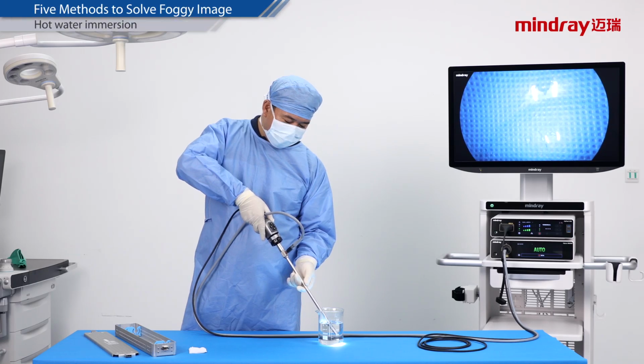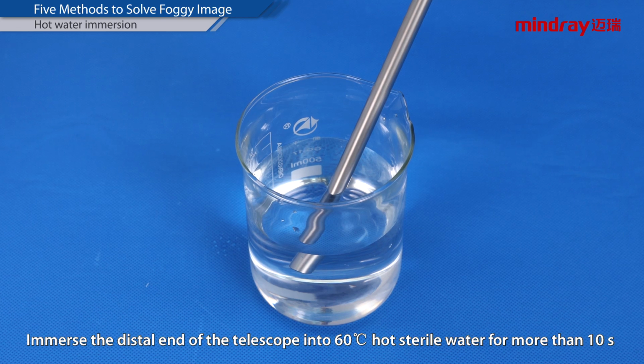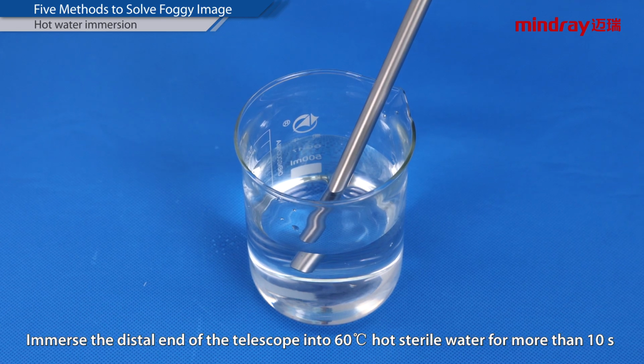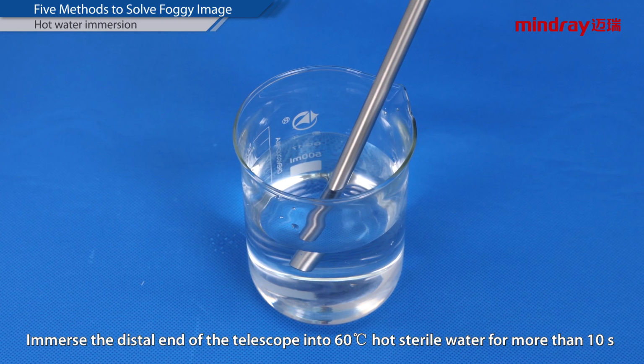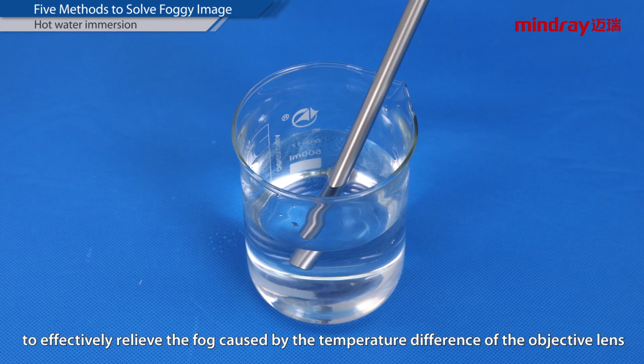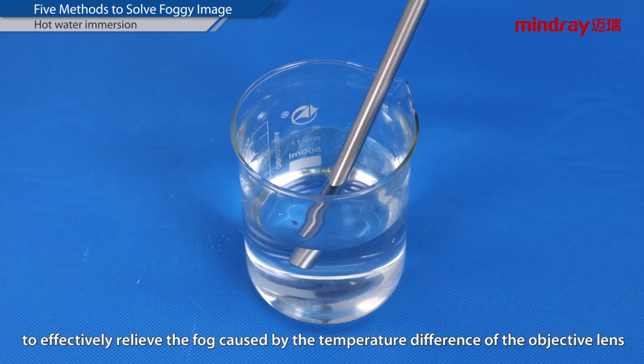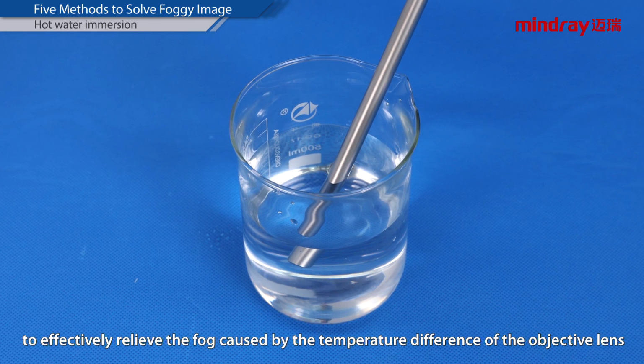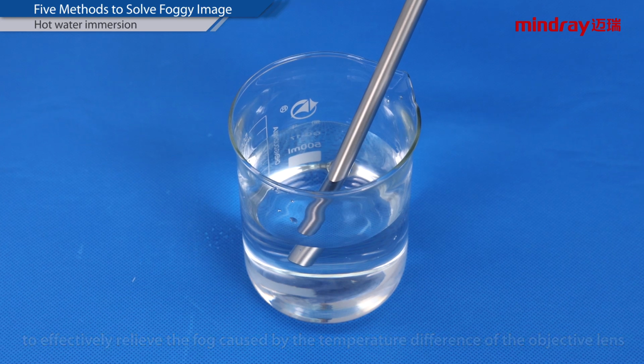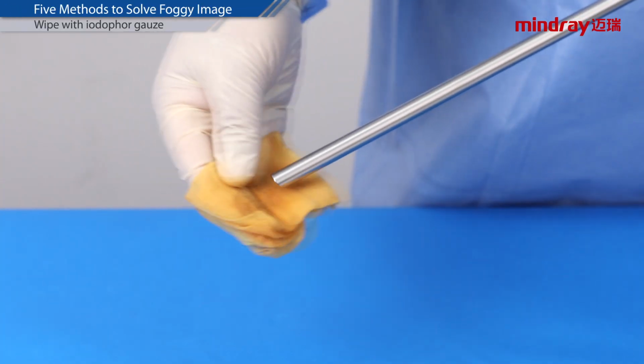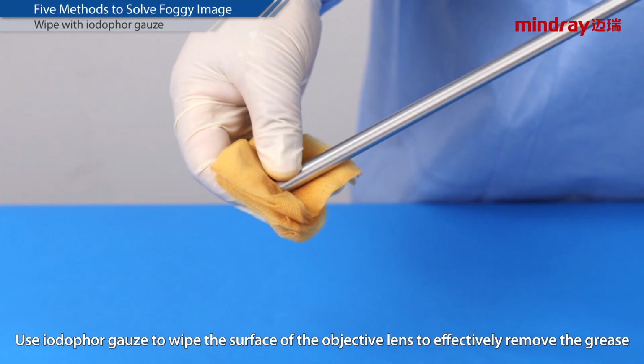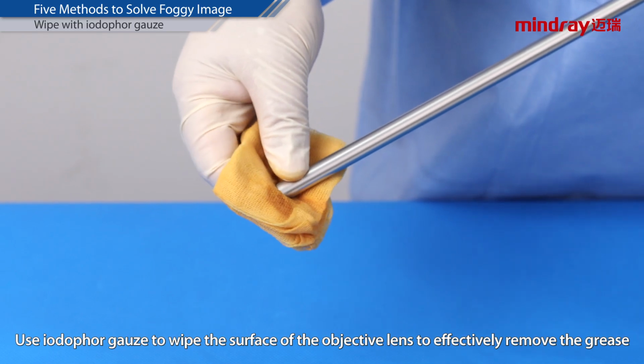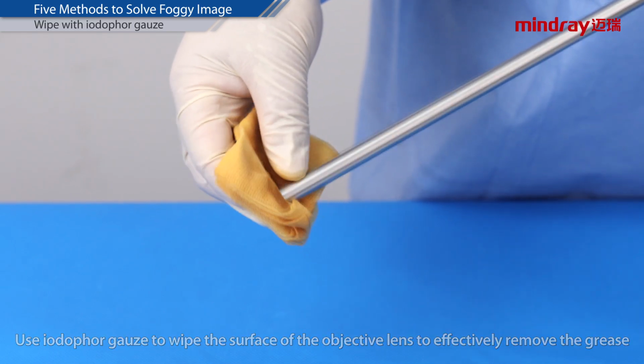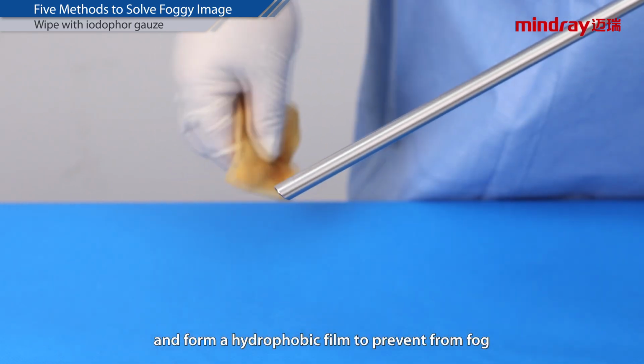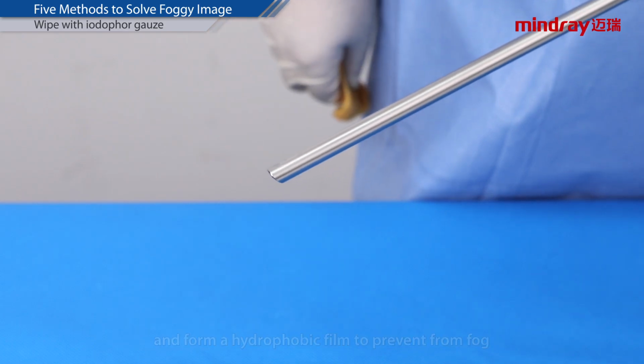Hot water immersion. Immerse the distal end of the telescope into 60 degrees centigrade hot sterile water for more than 10 seconds to effectively relieve the fog caused by the temperature difference of the objective lens. Wipe with iodophor gauze. Use iodophor gauze to wipe the surface of the objective lens to effectively remove the grease and form a hydrophobic film to prevent the fog.